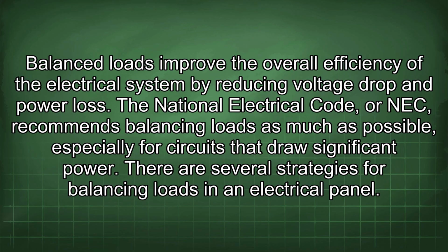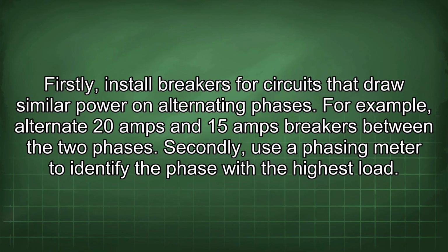The National Electrical Code, or NEC, recommends balancing loads as much as possible, especially for circuits that draw significant power. There are several strategies for balancing loads in an electrical panel. Firstly, install breakers for circuits that draw similar power on alternating phases. For example, alternate 20 amps and 15 amps breakers between the two phases.